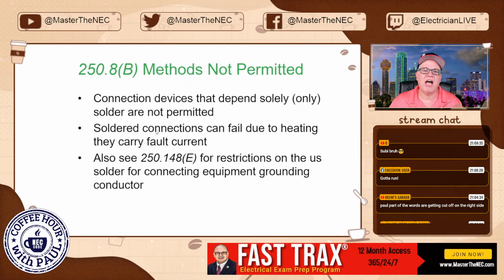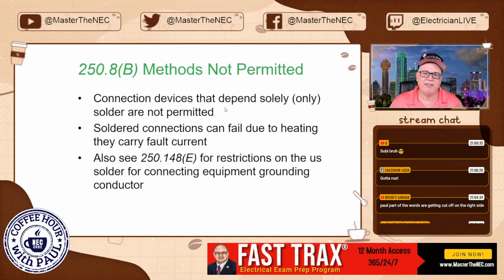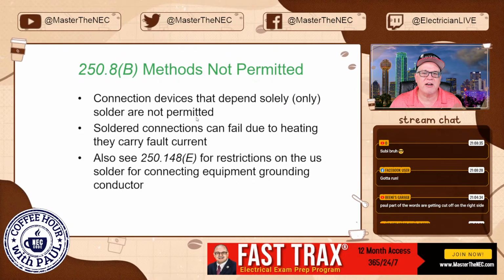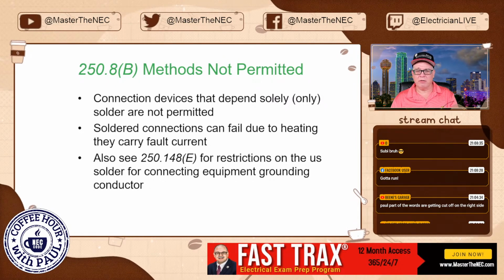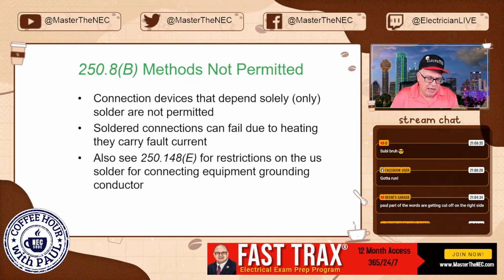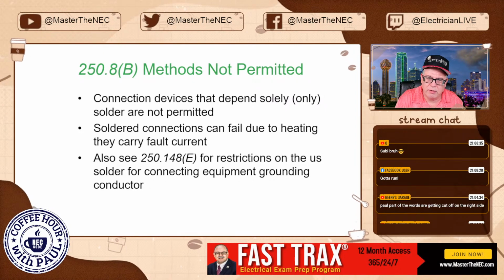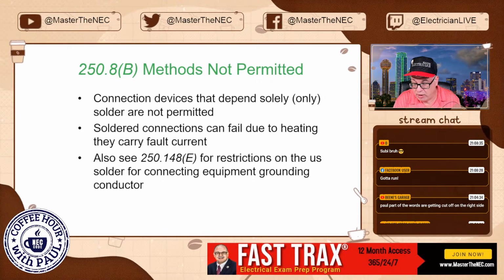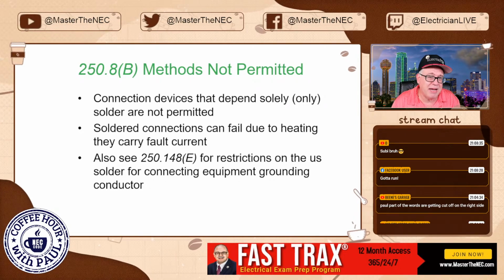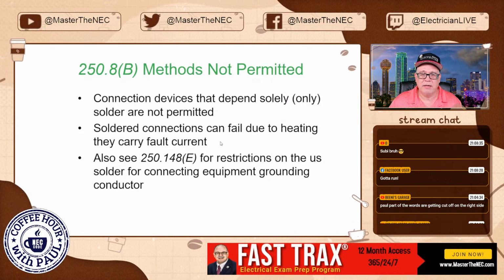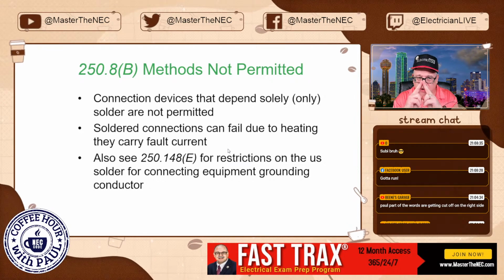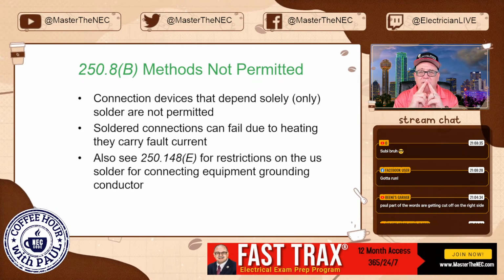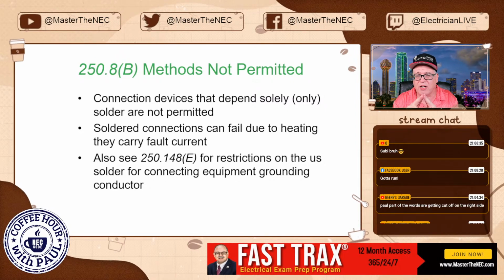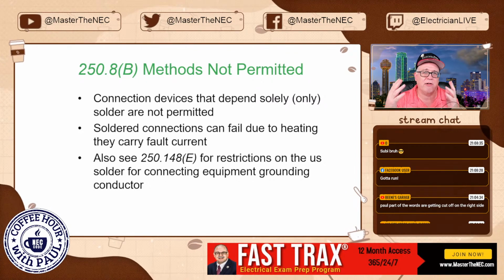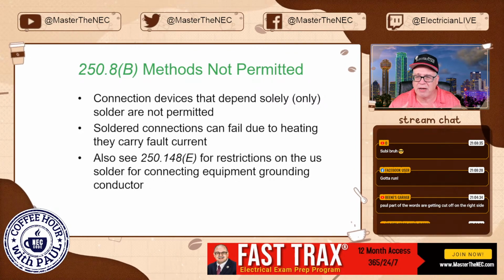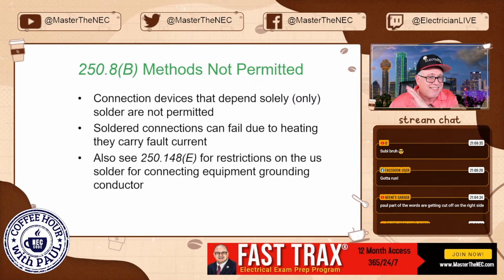All right. Methods that are not permitted, 250.8(B). Connection devices that depend solely only on solder are not permitted. Okay, now you can solder, but you can't be solely committed, okay, to just solder, right, to that connection. So you typically would pre-twist, and that would provide a mechanical connection prior to soldering, right? Now, if you're solely relying on soldered connections, they could be cold solder. They could come loose under heat cycling of the load through a conductor. Something can happen. They could pop loose, and then you open the integrity of your effective ground fault current path, right? So we want to make sure that we don't rely totally on soldering itself, okay?